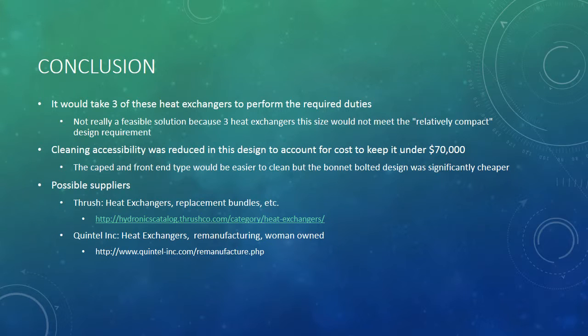Also, cleaning accessibility was reduced in this design to account for cost in order to keep it under 70 grand. The channel front end type would be easier to clean, but the bonnet bolted design was significantly cheaper. A couple possible suppliers we found were Thrush and Quintel.